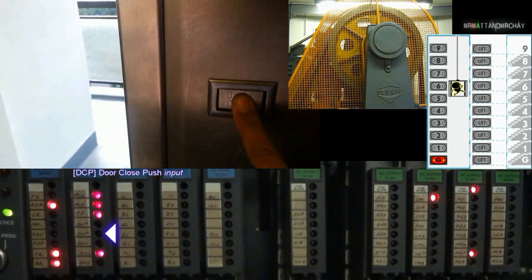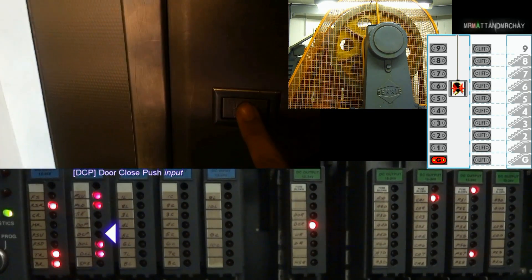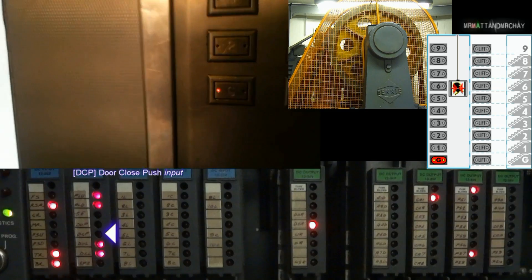DCP, this lift doesn't have a door close button. But if you observe this input, sometimes when the doors are closing, this input is also active.